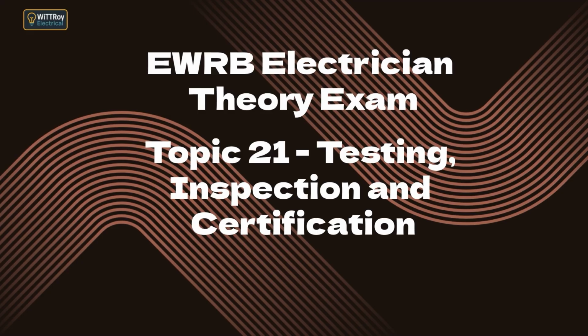Topic 21A. Define the terms testing, certification and inspection as prescribed in Schedule 1 of the Electricity Safety Regulations 2010. Let's define the three key terms. Testing means doing the physical electrical tests required by AS/NZS 3000 to confirm that installation work is electrically safe. This includes insulation resistance, polarity, earth continuity, earth fault loop impedance, RCD tests, and functional checks. Certification means completing the correct legal documentation, COC and ESC, to show the work is electrically safe and complies with the regulations and relevant standards.